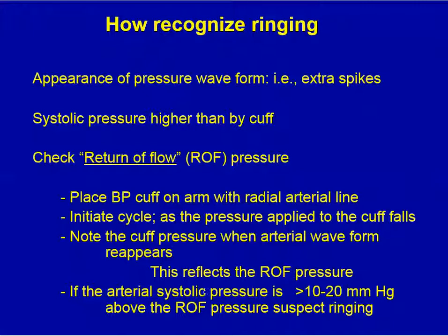If the arterial systolic pressure is 10 to 20 millimeters above the return of flow pressure, then you should suspect the presence of ringing.